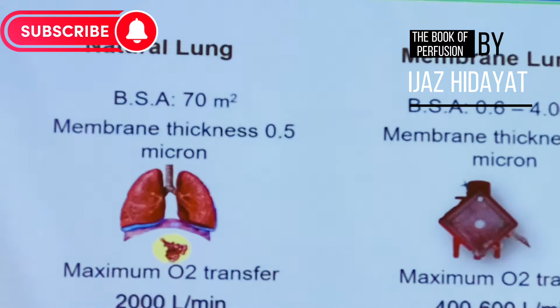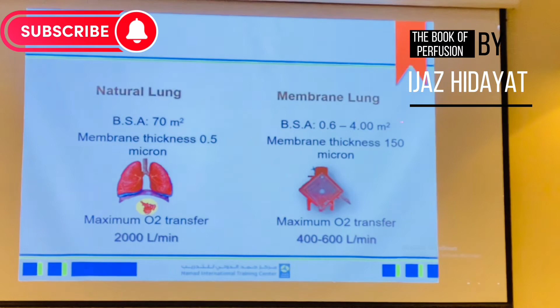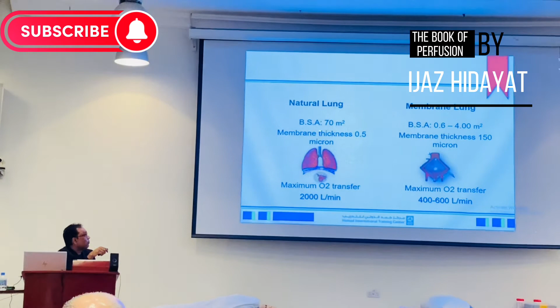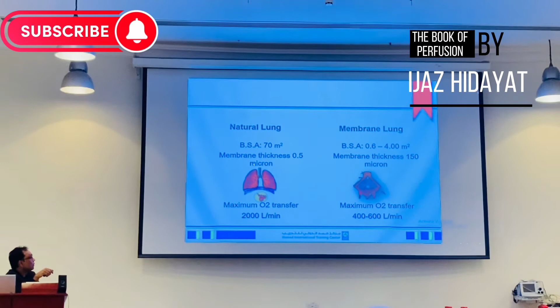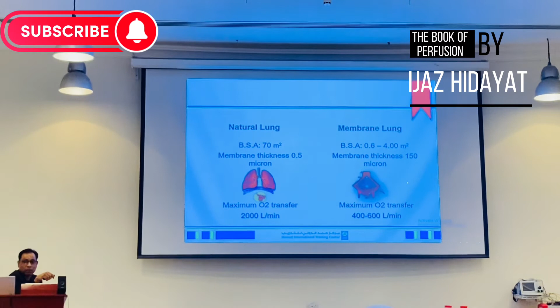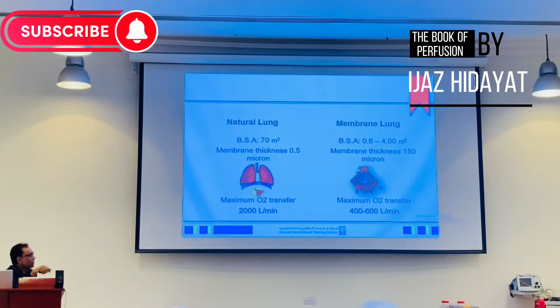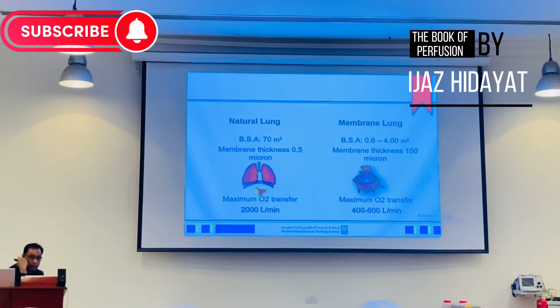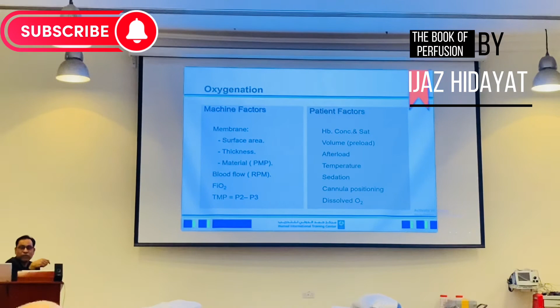There are two types of lungs, man-made and God-made. So what is the difference between the God-made and the man-made? The man-made lung body surface is only 0.6 to 4 square meters. Limited, we have some limited numbers. But the surface of the natural lung is 70 square meters. The thickness of the membrane is only 0.5 micron, but the man-made is 150 micron. The maximum transfer capacity with the natural lung is 2 liters per minute, but the man-made is only 4 to 600 liters per minute. This is a huge difference between what was made by man and the natural lung.